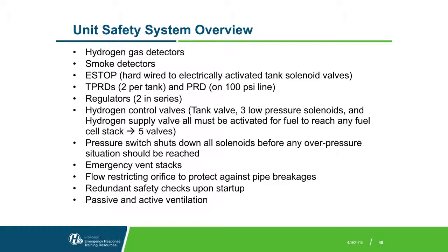Plus a pressure relief on the 100 psi line. Various regulators and control valves, pressure switches, the emergency vent stacks, again, pressure protection on the piping. Upon startup, the system goes through redundant safety checks. If it senses something's wrong, it's not going to complete the startup procedure and completely power up the unit. And then we have the ventilation.